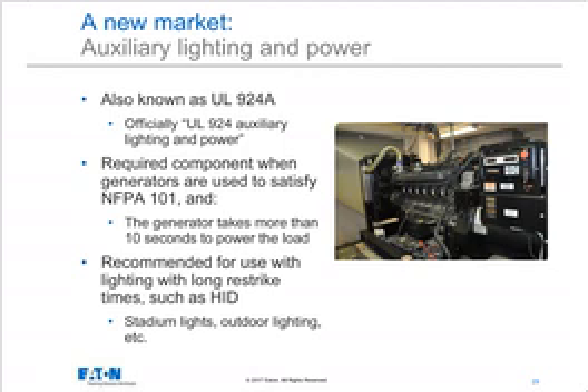So that's quite a bit of good news from the standpoint of not having to buy a lot of big, ugly, heavy batteries, but it also means that I'm going to need a generator. A lot of commercial buildings already have a generator, so that means they can be compliant with UL 924 for emergency lighting without having to buy 90 minutes worth of battery for their UPS. They can get away with a much more palatable 5 to 10 minute battery, maybe even a little less than 5 minutes. So a couple of frequently asked questions here.